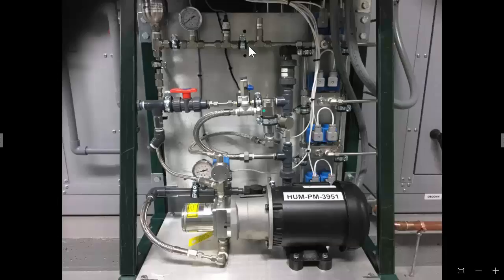And then there's this safety relief here, and that's in there in case there's another failure. Let's say that this particular sensor is broken and is not displaying the proper pressure out. This relief valve is set around 1400 psi, and it'll start to relieve a little bit of water through it to keep the pressure down. And then the gauge displays it all. That is a 0 to 2000 psi gauge. So typically you're just about straight up when it's running.